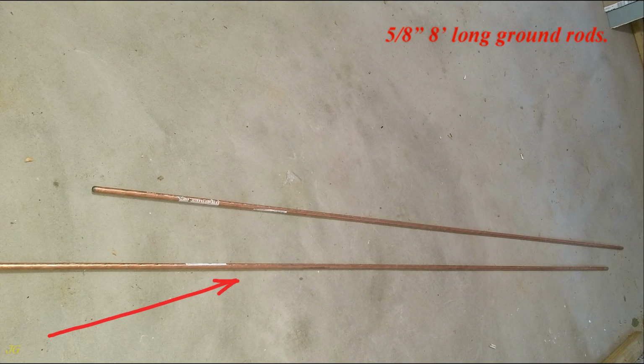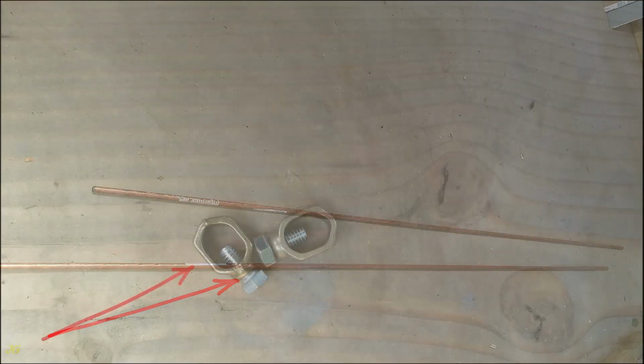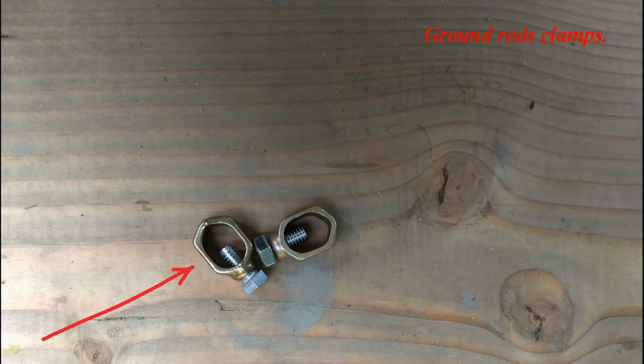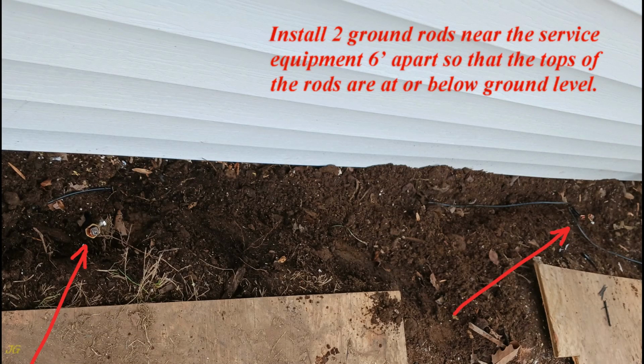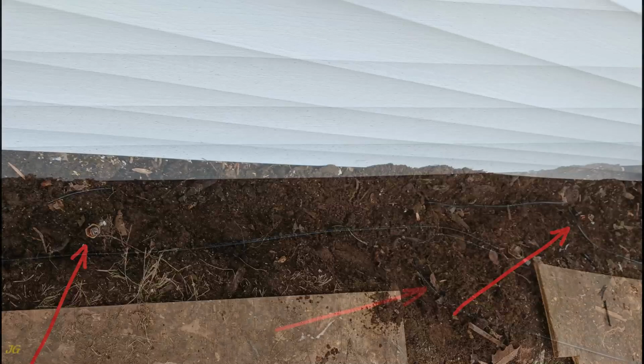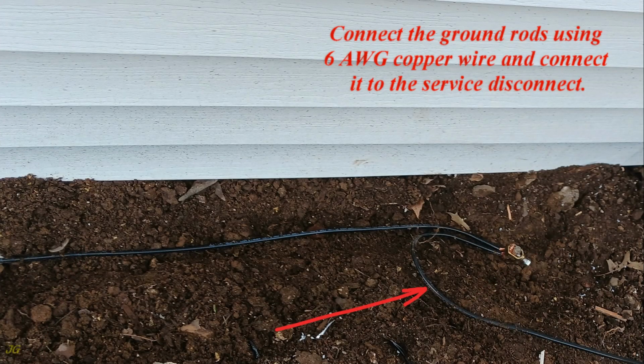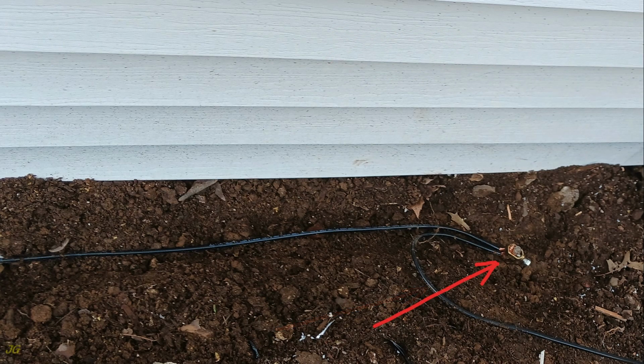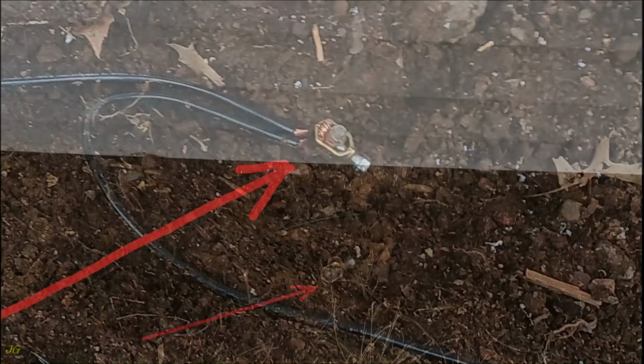5/8 inch, 8 feet long ground rods. Ground rod clamps. Install two ground rods near the service equipment 6 feet apart so that the tops of the rods are at or below ground level. Connect the ground rods using 6-gauge copper wire and connect it to the service disconnect. First ground rod continuously connected to a second ground rod.